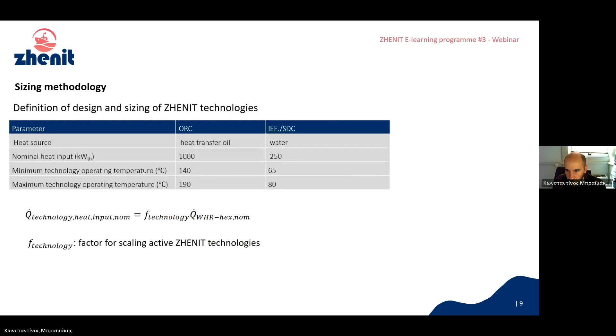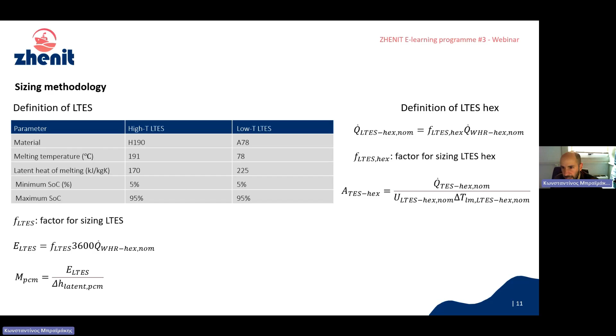Finally, another parameter that needs to be sized is the heat exchanger of this system. Inside the thermal energy storage system, we also have a heat exchanger, and this dictates the rate at which heat is supplied or removed from the thermal energy storage system. We follow a similar approach to the heat exchanger we used previously: we define an input and outlet nominal temperature for the heat transfer fluid, and based on overall heat transfer coefficients, we can calculate the area of this heat exchanger.